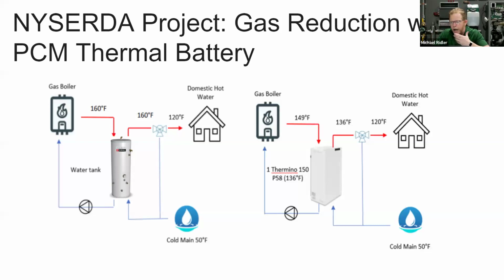So when we look at how we made the boiler more efficient, right off the bat, what happened was this Thermino battery used in this application would actually charge at about 140 degrees. So what they were doing is charging the battery at 149 degrees, storing the sensible and latent energy, whereas before the boiler was running at 160 degrees to charge the indirect to provide enough usable heat to the space. Not only did they prevent the boiler from running so much, shockingly, they were also able to make the boiler more efficient.